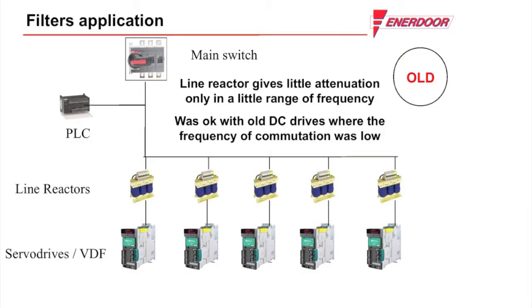Line reactors were originally designed for use with DC drives. Current AC drive designs incorporate IGBT transistors, which require the use of EMI RFI filters to deal with the higher frequency switching.